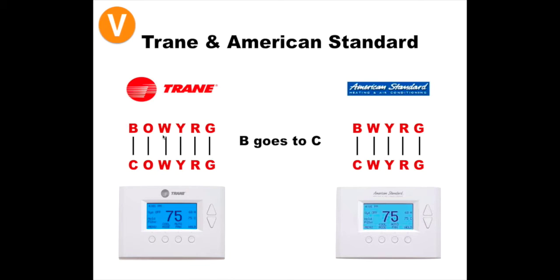transformer. Because what happens is if you wired this up wrong and you put this B wire into the B terminal on our thermostat, what will happen is the second you turn power back on, the fuse will blow, because the R wire on our thermostat will eventually energize the B terminal on our thermostat. And if you ever have an R and a C wire touch, that's a direct short on the transformer, and that's going to be a blown fuse or a transformer every time that happens. So keep that in mind. You always want to make sure that on Trane and American Standard, the B goes to C. And again, just always ask questions, make phone calls, look at your tech binder, and that will save you a lot of headaches.